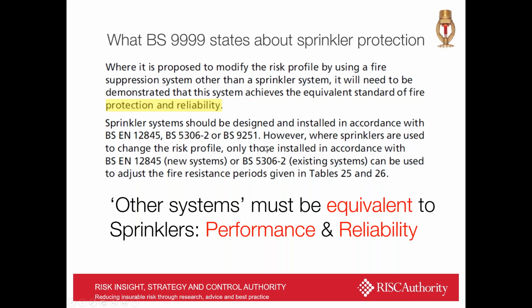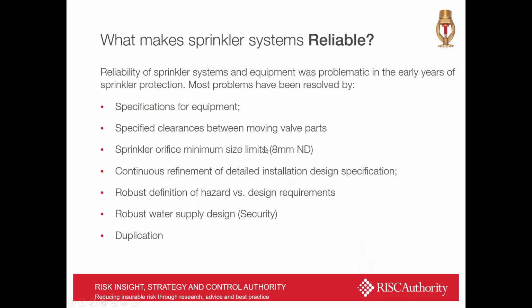But if we hold on to that thought, we probably need to consider what makes things reliable. Now, I don't want to enter into an all-out sprinkler versus Watermist debate, but it's sort of inevitable in some respects to visit here. It's a good benchmark because sprinklers probably are the most reliable suppression system that we have. And generally, when asked to operate within the figures, most analyses show them to be over 90%, 96% likely to function properly when called upon to do so, which is an enviable figure which no other type of suppression system comes close to.